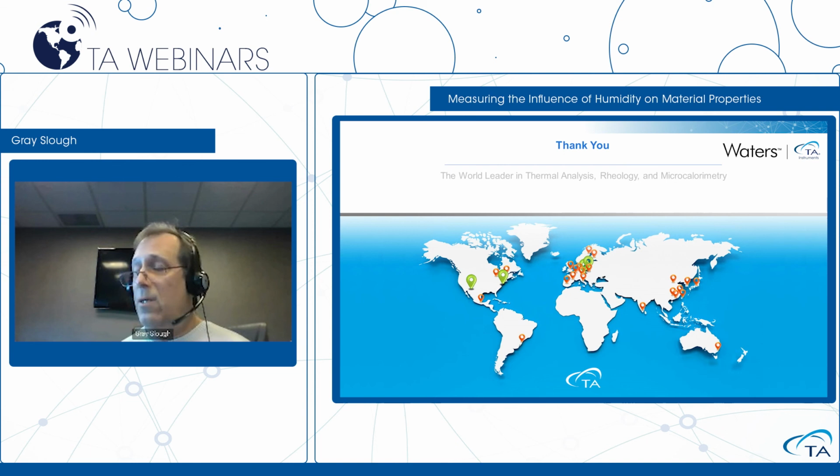That probe will be used to calibrate the system for dynamic experiments, and that allows me to correct something earlier, that that's an additional calibration that would be done on the TMA RH, is to use that probe to calibrate for dynamic experiments. But you can also use it again to make measurements of samples in that type of configuration.